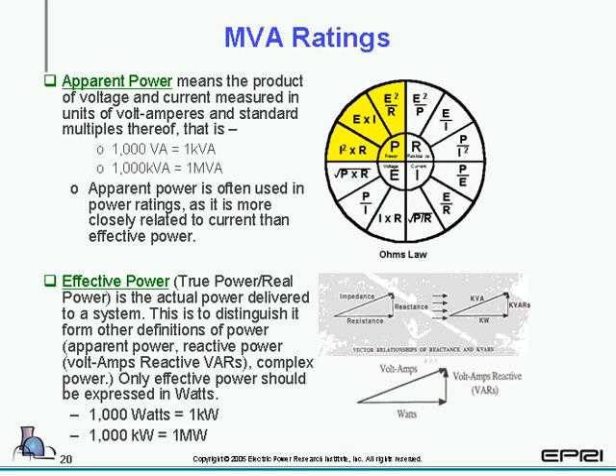Go ahead. The next one we look at gets a little more difficult in the understanding of them. We're going to be looking at the VA ratings, or as it's written at the top, the MVA ratings. You have two that we're going to be looking at. The first one is apparent power. It means the product of the voltage and the current, measured in units of volt-amps and in standard multiples thereof. Apparent power is often used in power ratings as it is more closely related to current than effective power. Effective power, true power, is the actual power delivered to the system, and it is measured in watts. This is the only expression of true power.